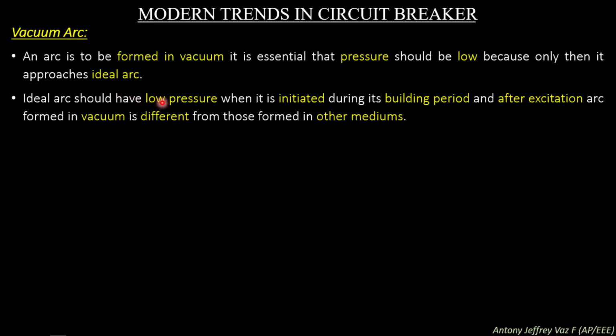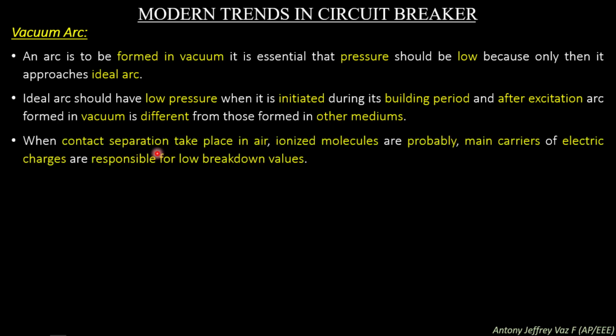An ideal arc should have low pressure when it is initiated, during its building period, and after excitation. An arc formed in vacuum is different from those formed in other mediums. So on comparing the ideal arc with the vacuum arc, the characteristics of the arc in a vacuum are very different, and so a different theory is related to arc formation in vacuum. When contact separation takes place in air, ionized molecules are probably the main carriers of electric charges and are responsible for low breakdown voltages. So when the contacts are separated in air, the ionized molecules present in the air are the majority charge carriers and they create the arc.